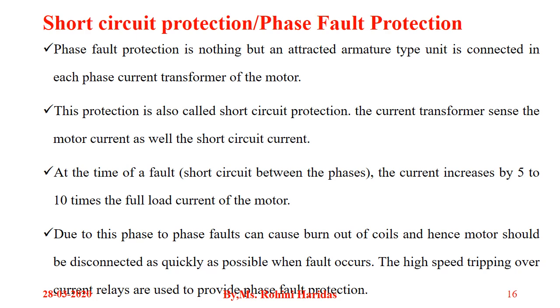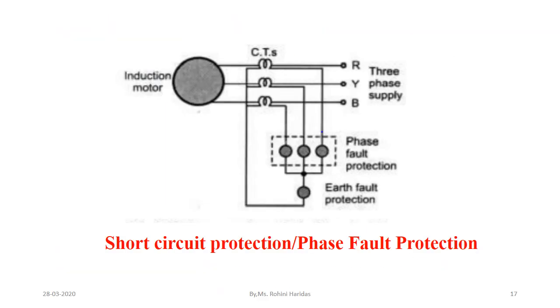CTs are connected in each phase and phase fault protection relays — which are overcurrent relays — are connected in the CT secondary. Under normal operating conditions, the CT secondary current is within the permissible rated limit and the relay does not operate. If a fault occurs, the primary current increases to a high value, the CT secondary current also becomes very high, and if it exceeds the preset value, the overcurrent relay operates, providing protection against short circuits and phase faults.